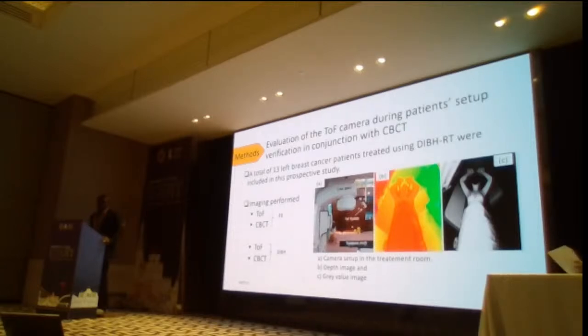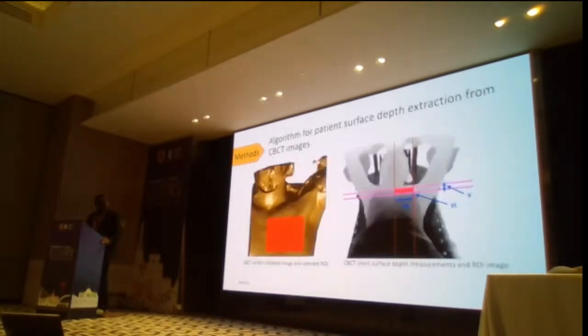Figure B shows an example of a depth image obtained from the TOF camera, which is used for our data analysis. Figure C is an example of a gray value image obtained from the same camera, which is used for general patient surveillance and also selection of the region of interest, because, as you can see, it is clearer than the depth image. We developed an algorithm using MATLAB for patient surface depth extraction from CBCT images, because the TOF camera provides a surface image while the CBCT images provide only slices. So in order to match the two imaging methods, we developed an algorithm that gives us the capability to measure patient chest surface depth from the CBCT image.